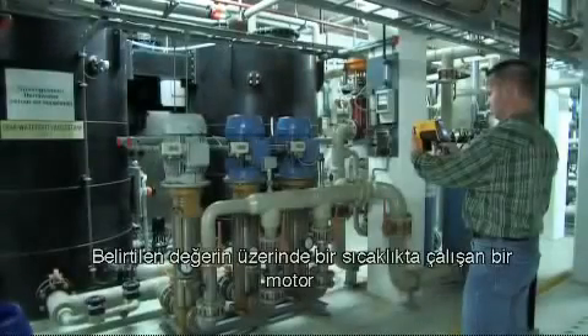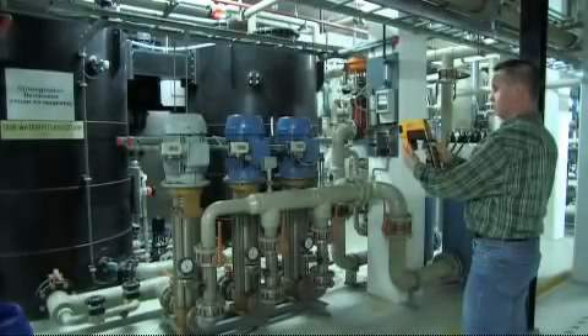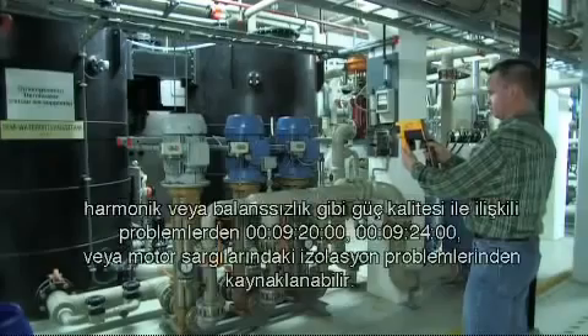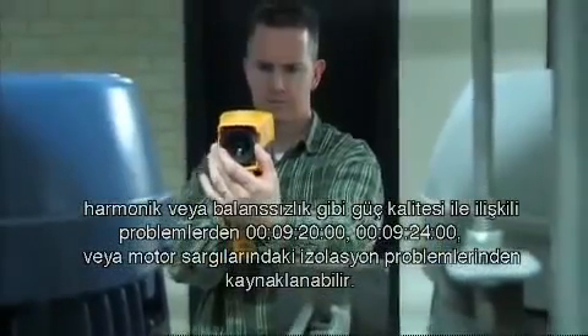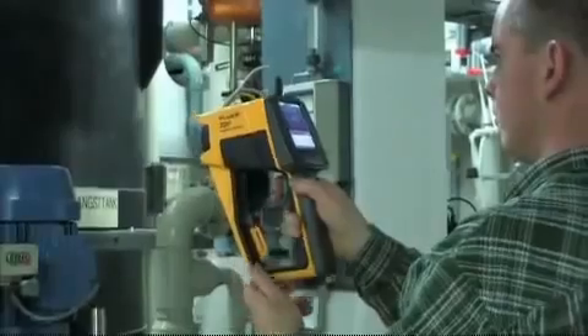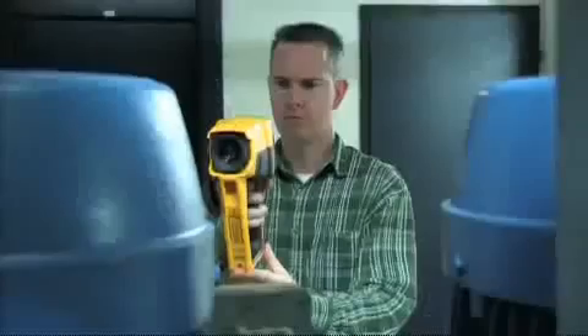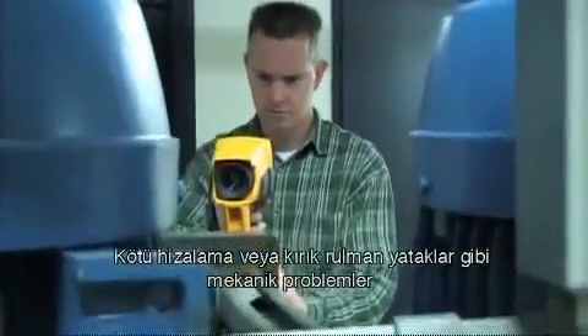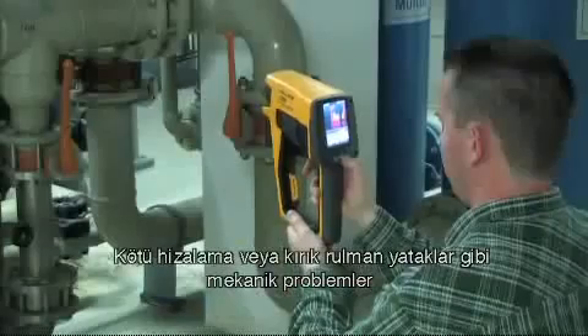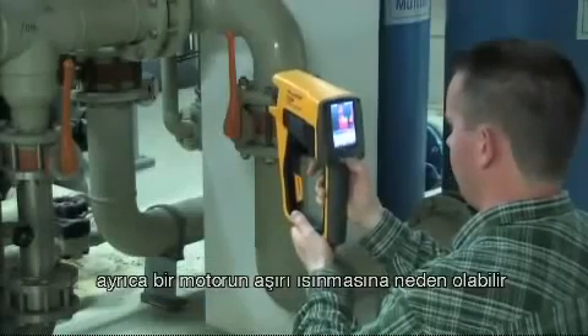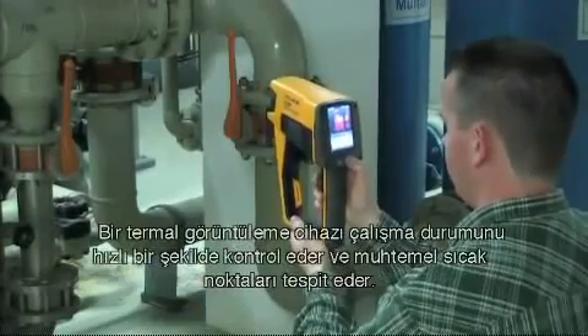A motor running at higher temperature than specified may be due to bad cooling, power quality related problems like harmonics or unbalance, or insulation problems with the motor windings. Mechanical problems such as bad alignment or broken ball bearings could also cause a motor to overheat.